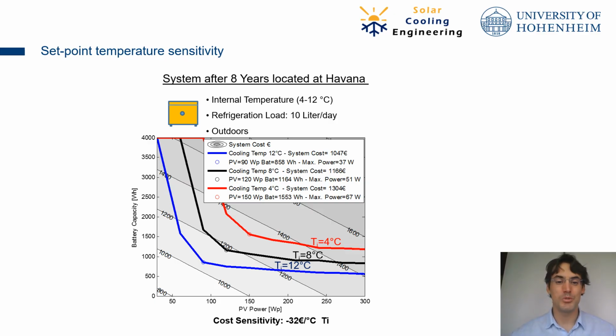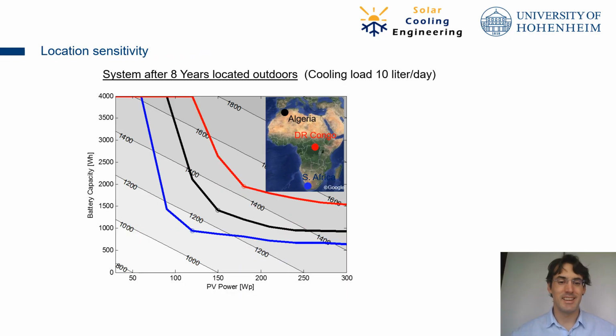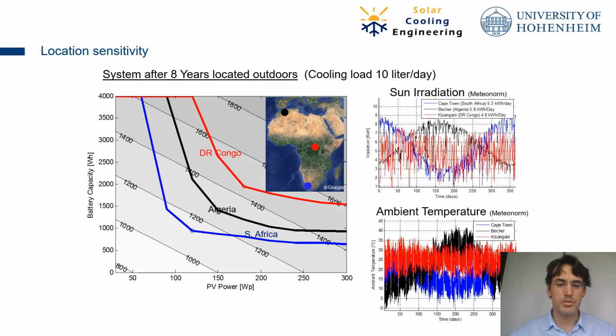Most of you are probably also expecting the sensitivity of the location, right? It's not the same to be in one country versus another, to have a subtropical or tropical weather, or to be in the mountains. This affects the design too - if you are in the mountains, the ambient temperature is lower, so batteries and PV panels can be smaller because energy consumption is lower for the same cooling. I wanted to bring 3 different scenarios - South Africa, Algeria, and Congo - with very different sun irradiation.